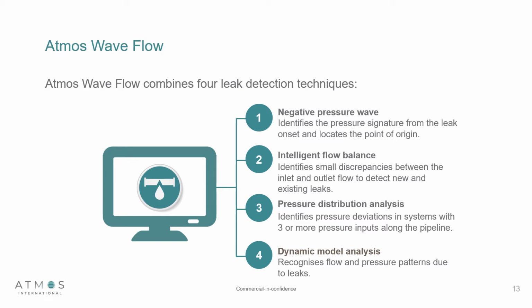We also combine this with dynamic model analysis. This is slightly different to Atmos Pipe. Atmos Pipe is using probability to determine if the operation it's seeing is a genuine leak event or it's something that's naturally occurred in the pipeline. What Waveflow utilizes is pattern recognition. When a leak occurs, it generates a very unique pattern with how the pressures and flows change. When the leak detection system sees this, it will alarm very, very quickly. Utilizing pattern recognition means we can detect leaks in minutes rather than tens of minutes.